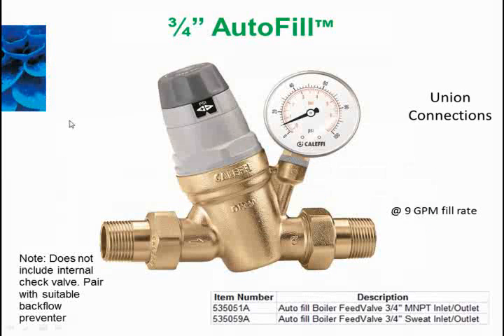Now, one of the things that we brought that valve on, guys said, well, on the commercial jobs, we'd like to have a little faster flow rate because we've got a lot of piping to fill. We've got a big building to fill. Can you give us a bigger version of that? So we did. We came out last year with a 3/4 version of that, which will fill almost twice the rate of the half-inch, so it goes up to about 9 GPM fill rate.